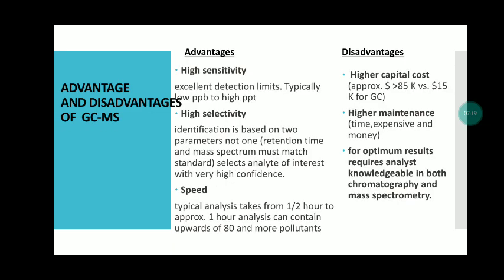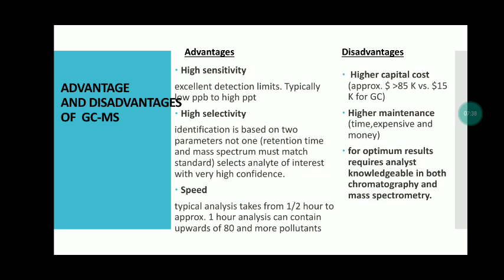Advantages and disadvantages of GCMS. Advantages: high sensitivity with excellent detection limits, typically from low ppb to high ppt; high selectivity, as identification is based on two parameters — retention time and mass spectrum — which must match a standard, allowing selection of analytes of interest with very high confidence; speed, with typical analysis taking from half an hour to approximately one hour. Disadvantages: higher capital cost, higher maintenance, and for optimum results, requires analysts knowledgeable in both chromatography and mass spectrometry.